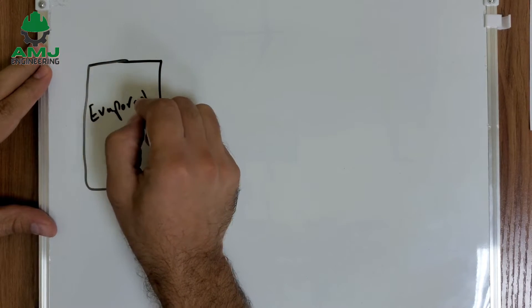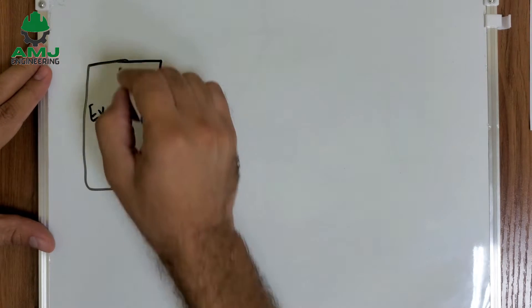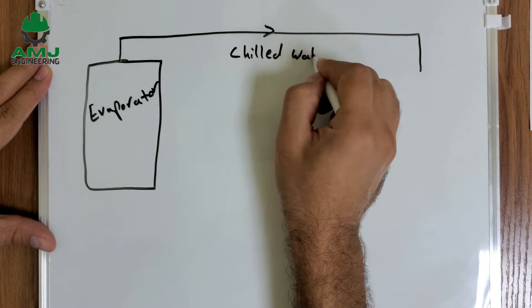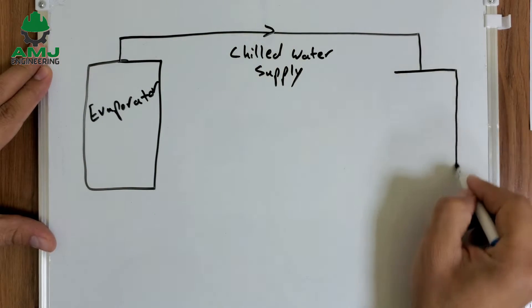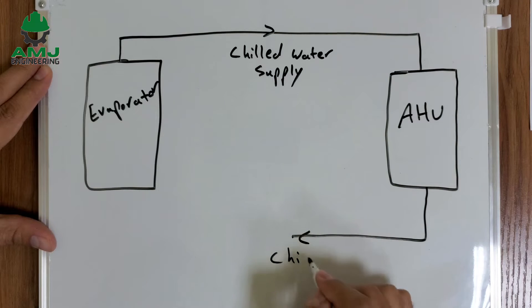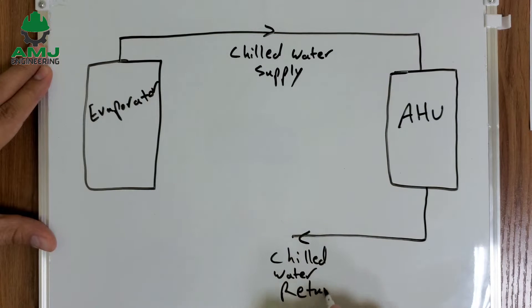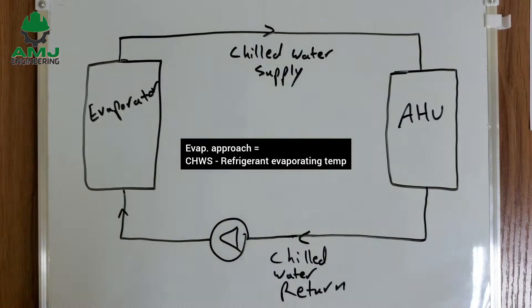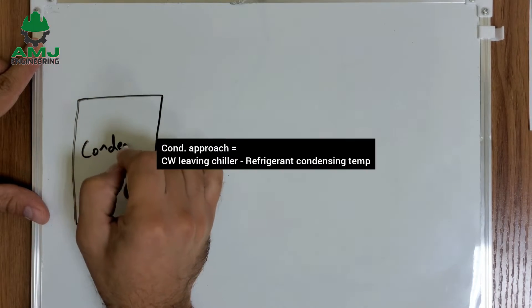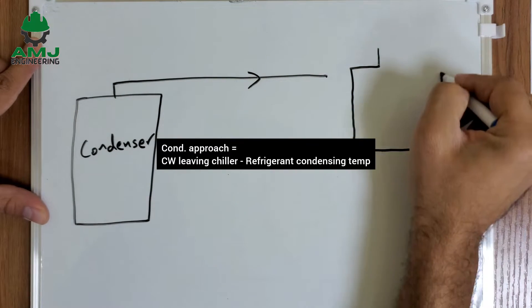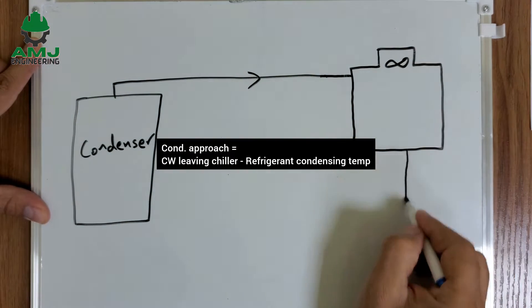What is chiller approach? Chiller approach is the temperature difference between the water and the refrigerant. Because there are two heat exchangers in a chiller, we have two types of approach: evaporator approach, which is the temperature difference between the chilled water supply and the evaporating refrigerant, and condenser approach, which is the temperature difference between the condenser water leaving the condenser and the condensing refrigerant.